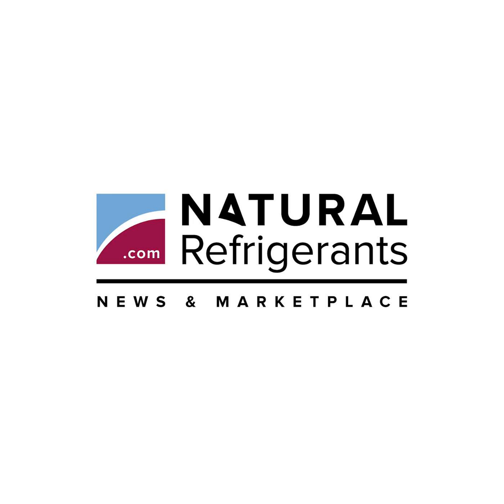In addition to being used globally in most commercial display cabinets, in Europe, propane is increasingly employed in commercial and industrial chillers, as well as in residential heat pumps and some home and auto air conditioning systems. The latest version, the 7th edition of the global IEC 60335-2-40 HVAC standard, approved in 2022 and used as a model by individual regions and countries, allows up to 988 grams, 2.2 pounds, of R290 in HVAC units located indoors or connected to the indoor space, such as ductless split ACs or ducted central systems. These are subject to room size limits and other equipment design requirements. It also allows 4.94 kilograms, 10.8 pounds, of R290 in outdoor/indirect systems, such as air-to-water monoblock heat pumps, among other limits.